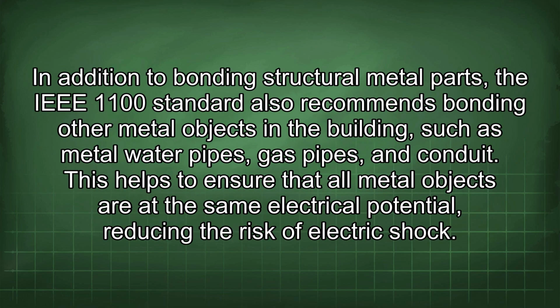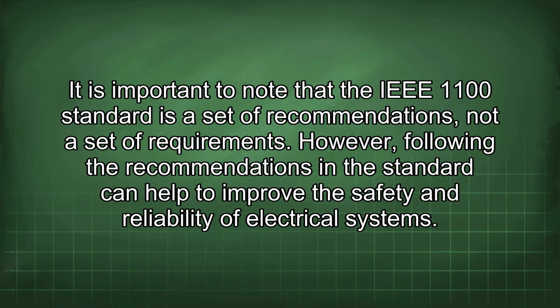In addition to bonding structural metal parts, the IEEE 1100 standard also recommends bonding other metal objects in the building, such as metal water pipes, gas pipes, and conduit. This helps to ensure that all metal objects are at the same electrical potential, reducing the risk of electric shock. It is important to note that the IEEE 1100 standard is a set of recommendations, not a set of requirements. However, following the recommendations in the standard can help to improve the safety and reliability of electrical systems.